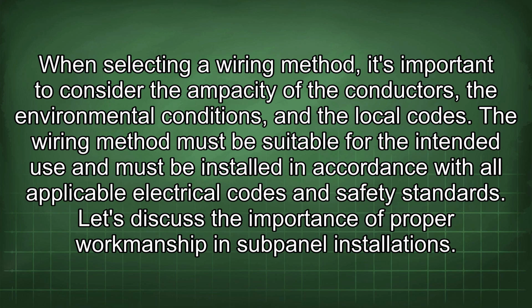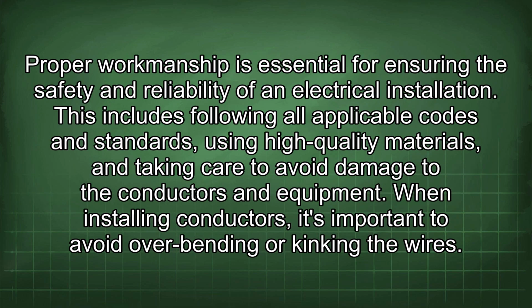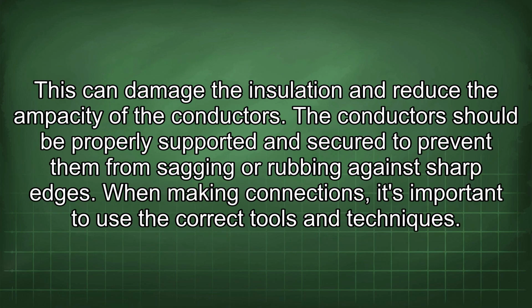Let's discuss the importance of proper workmanship in subpanel installations. Proper workmanship is essential for ensuring the safety and reliability of an electrical installation. This includes following all applicable codes and standards, using high-quality materials, and taking care to avoid damage to the conductors and equipment. When installing conductors, it's important to avoid overbending or kinking the wires. This can damage the insulation and reduce the ampacity of the conductors. The conductors should be properly supported and secured to prevent them from sagging or rubbing against sharp edges.